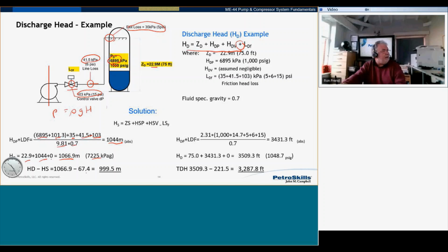Now remember, we had 67.4 on the suction, 1,066 on the discharge, which gives us a total dynamic head of 999.5 meters. Fantastic. This has given me an operating point. So for that particular flow, I've got that particular amount of friction loss. The pressure head and the elevation heads do not change with flow, so don't worry. It's only the friction head that changes.